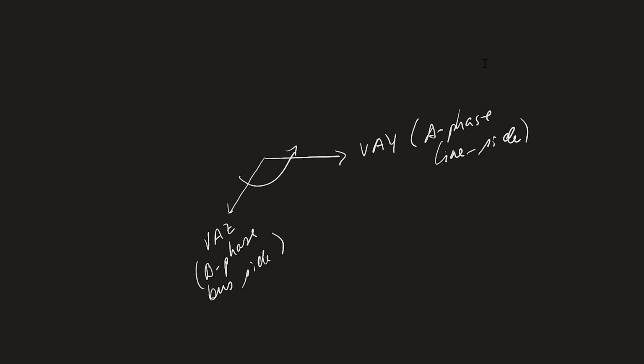Now I mentioned before that the synchronizing voltage doesn't have to be single phase, it could also be phase to phase. So for example, if we were using the B to C voltage from the bus side and we wanted to compare that to the A phase on the line side, we would need to compensate for both the phase shift and the magnitude difference because of course the phase to phase voltage nominally is going to be square root of 3 higher than the phase to neutral voltage. So we would also need to compensate for the magnitude.